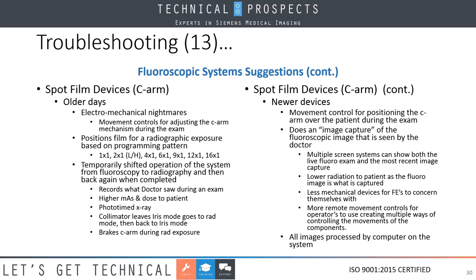Because basically what happens is the doctor is going over the patient, he sees something, and how simple it was for the doctor is he just rotated a handle in some cases. Once that happened, we stopped the fluoro image, the film came into the beam, the tube went into a radiographic mode, we shot an x-ray that we phototimed, and at the completion of the x-ray, the system shut down, the film went back, and now went back into the fluoro mode. So I only had one chance to get a perfect x-ray. That's why we used phototiming. So now I had to ensure that all my phototiming was properly calibrated because I only got one shot to do this.